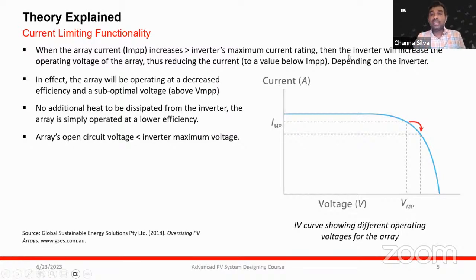So simply, the inverter will shift the power point to a different position to get into a comfortable zone where the inverter can work. It is trying to reduce the maximum power point current, but in parallel the voltage of that point is being increased. How is it doing that? By decreasing the efficiency.